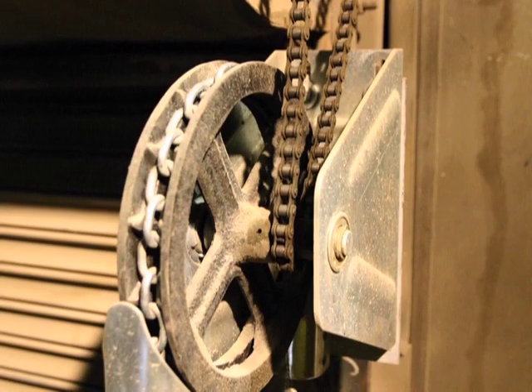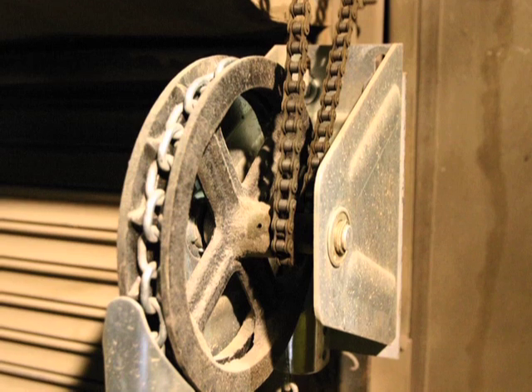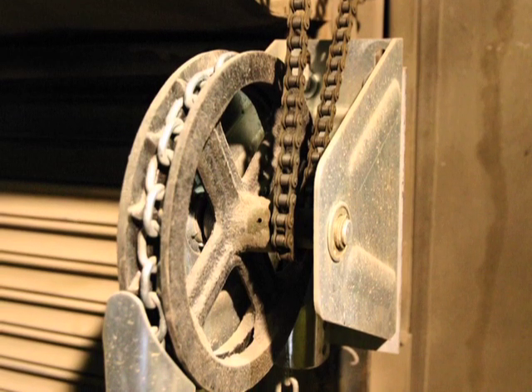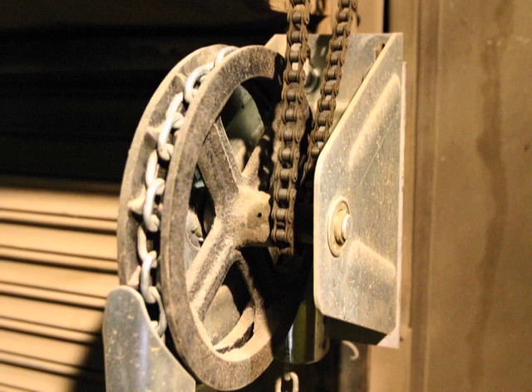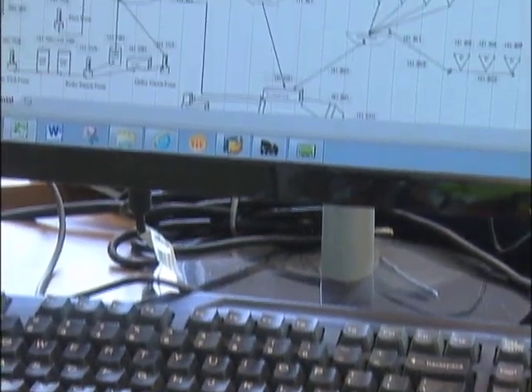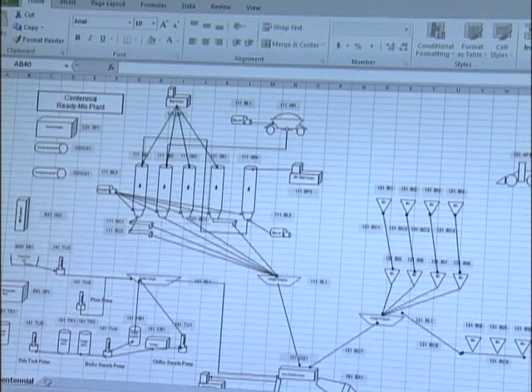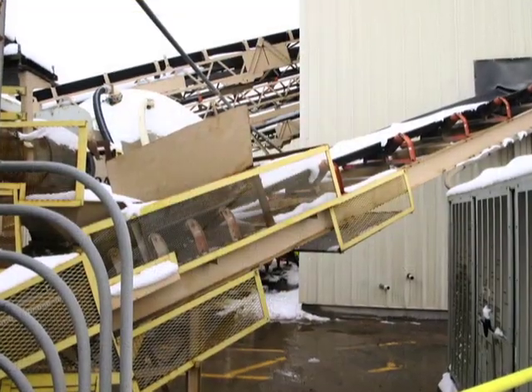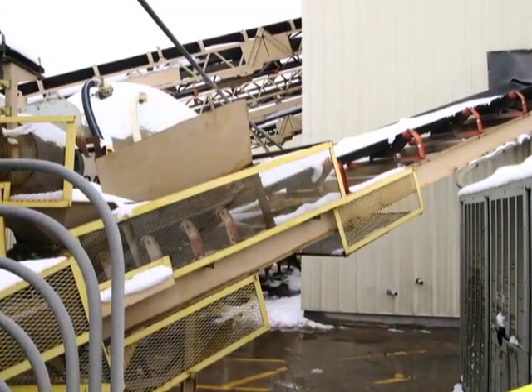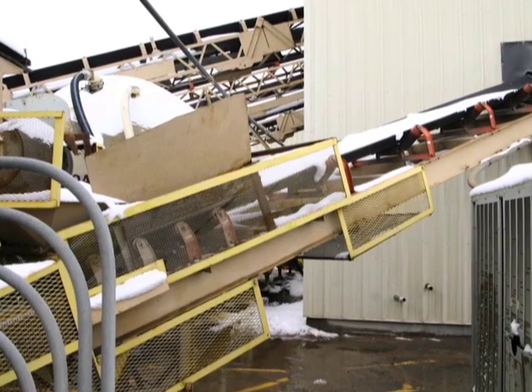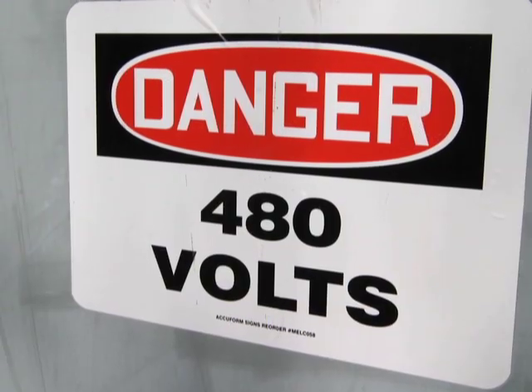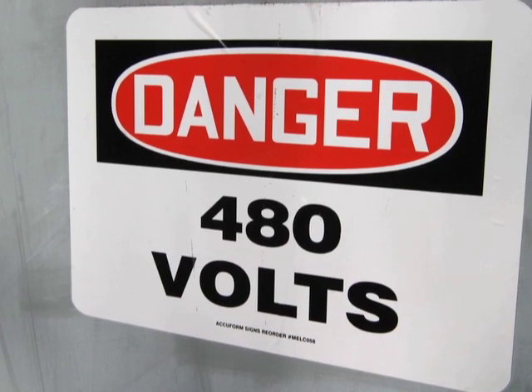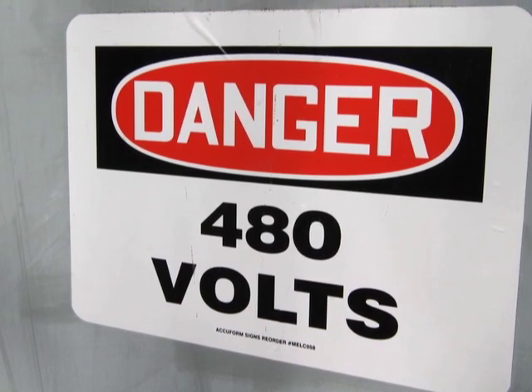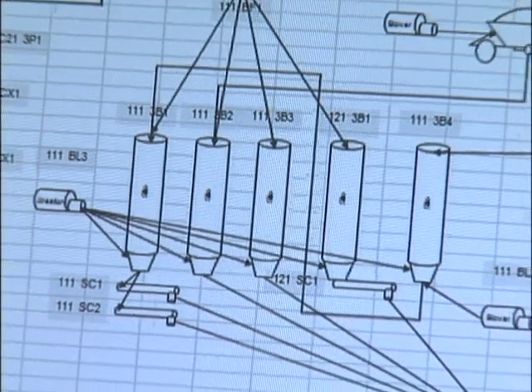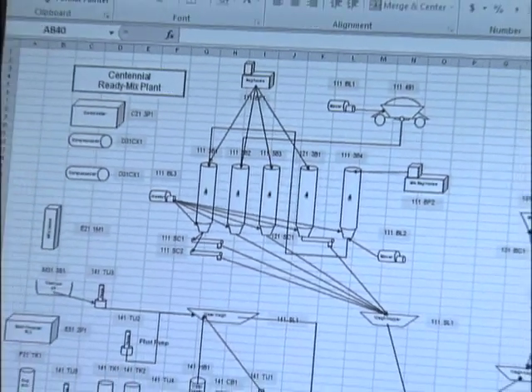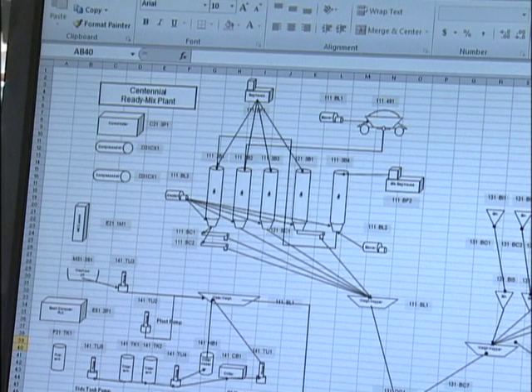Mechanical energy will often be found in motors with chains, sprockets, or belts associated with the powering of a conveyor or other equipment in the plant. Now, as you can see, there are multiple sources of energy powering equipment. Every plant layout, location of sources of energy, pieces of equipment, and the types of equipment may be very different. No matter the variations, you must have a plant layout map or a diagram of equipment location, and then written lockout, tagout, and tryout procedures for every piece of equipment requiring hazardous energy control.